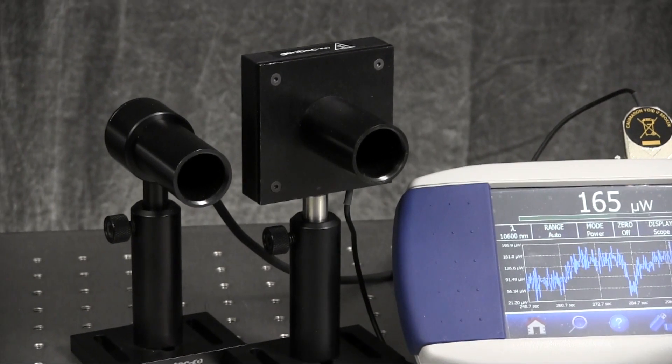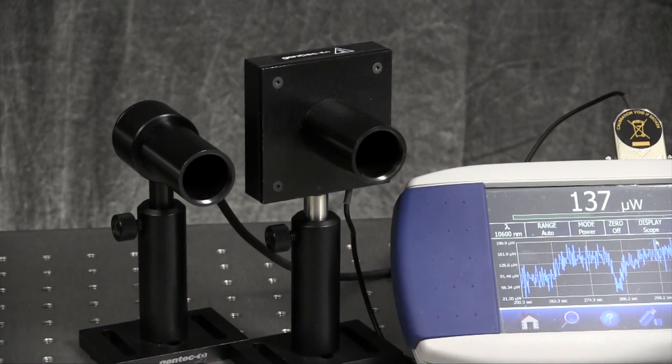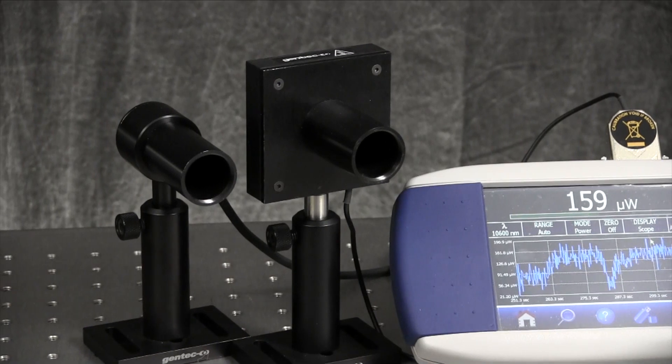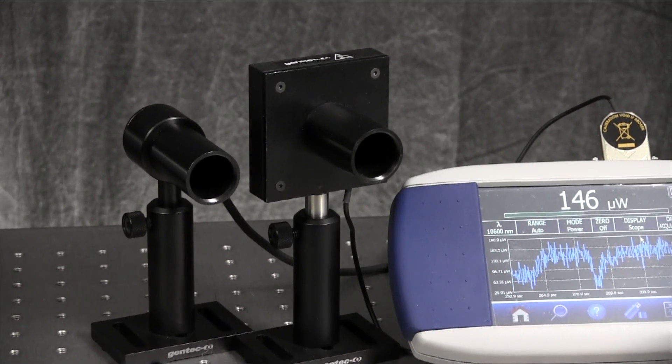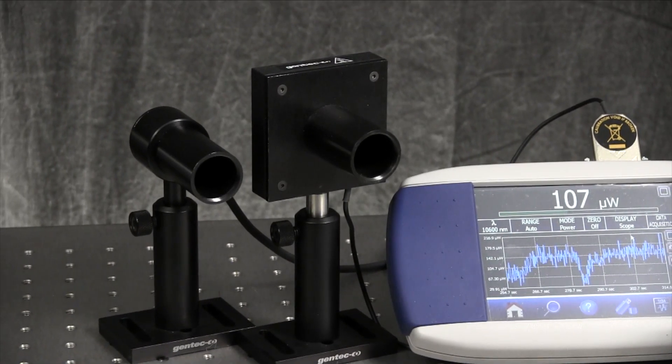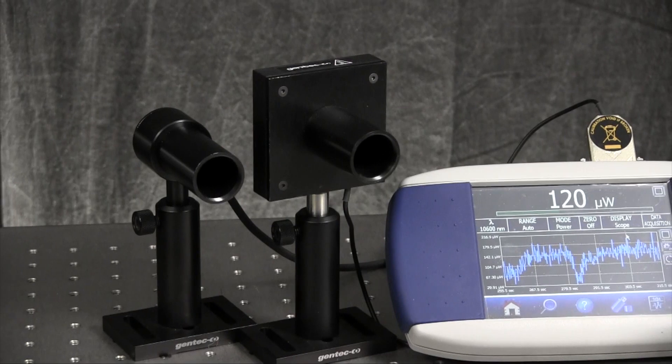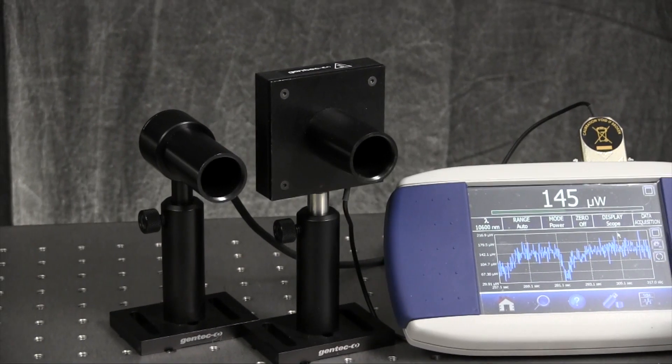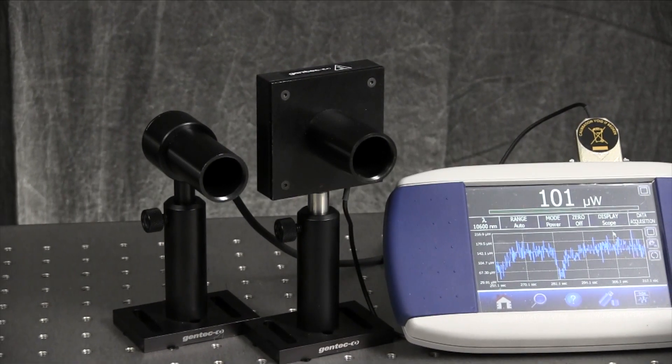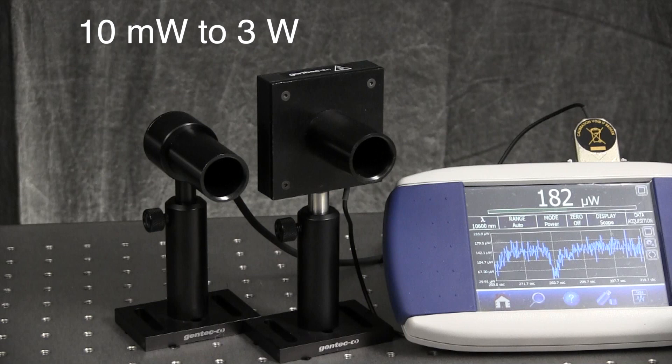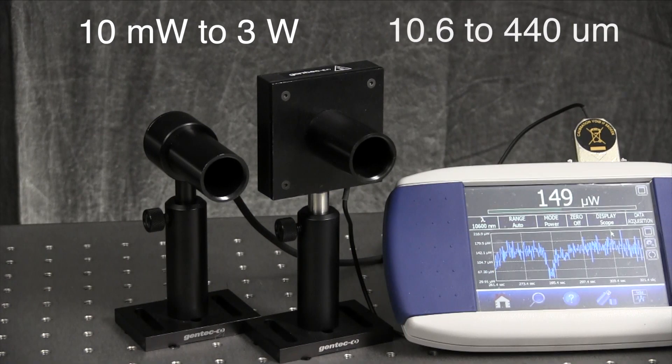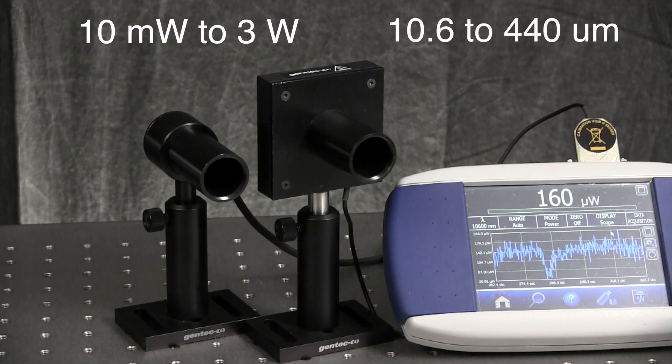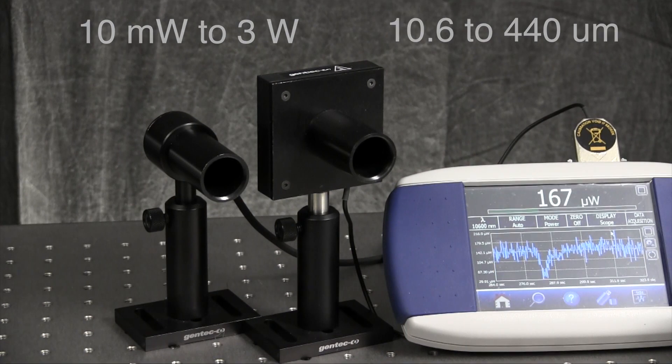The terahertz 12d thermopile does not require a chopper and can be used to measure the power of a CW terahertz source and the average power of a pulsed or modulated terahertz source from 10 milliwatts to 3 watts. It boasts a flat spectral response from 10.6 to 440 microns.